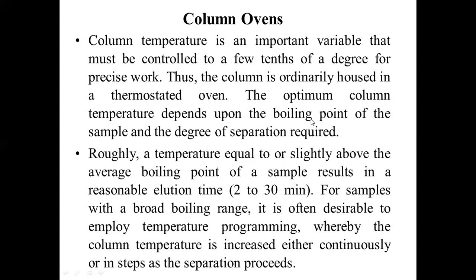This programming is possible because of the role played by the oven, right? The column oven should be thermostatically controllable. We must be able to adjust the required temperature, then only is it possible to program the temperature. Otherwise, it will be impossible. This thermostatically controllable oven is most suitable to adjust the temperature in a reasonable elution time of 2 to 30 minutes, so we can have serial elution of the solutes one by one.